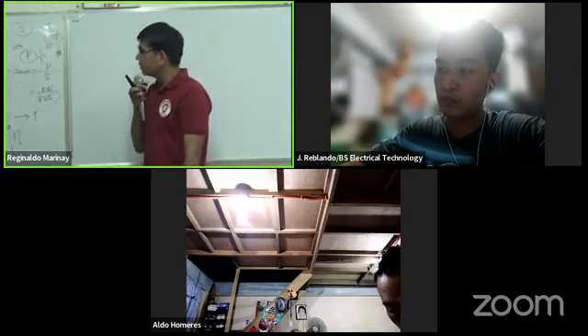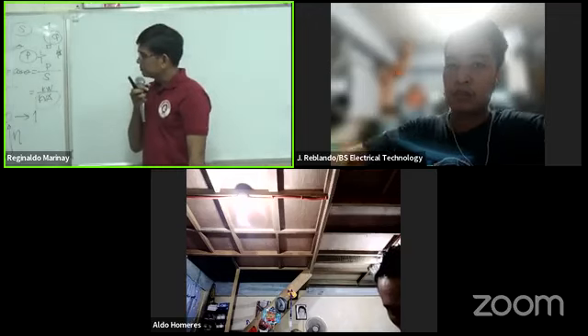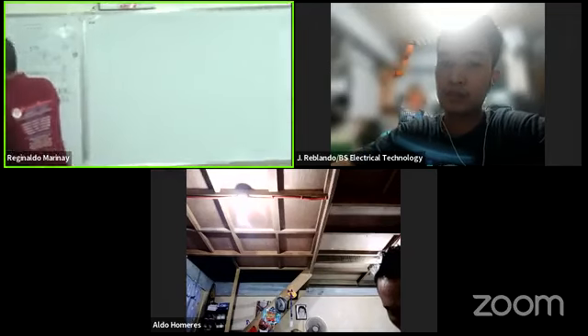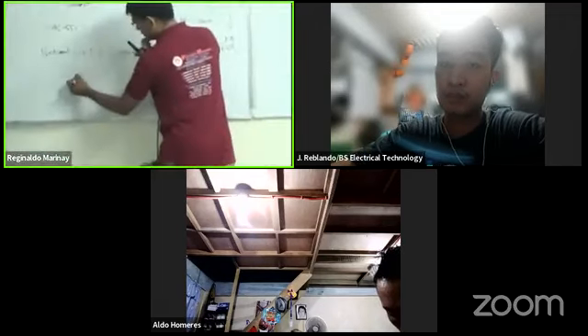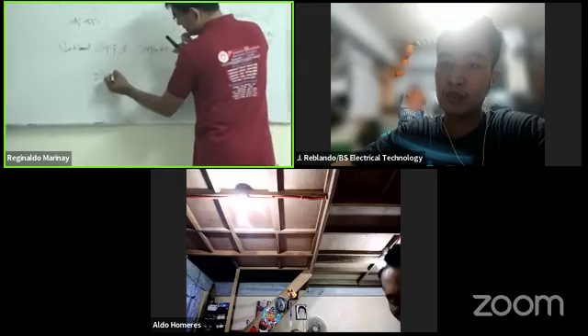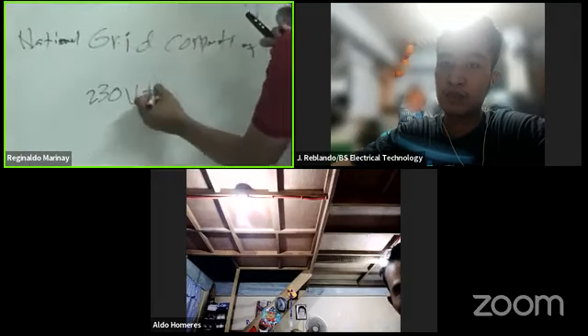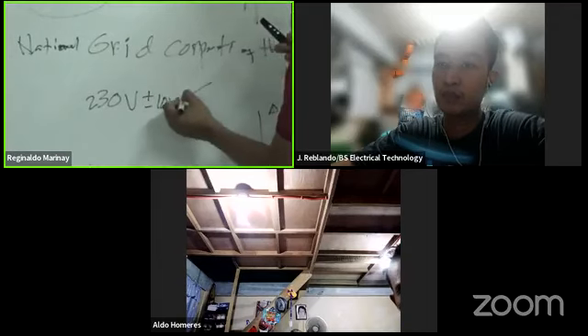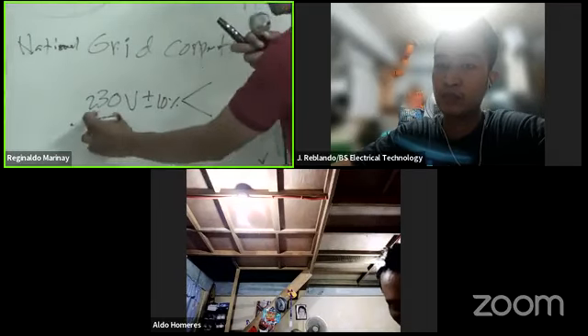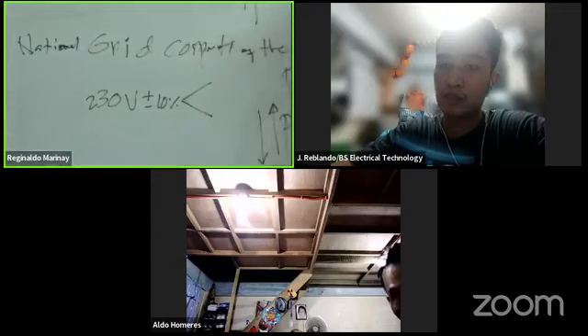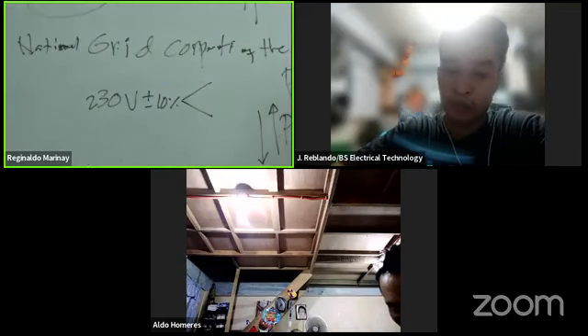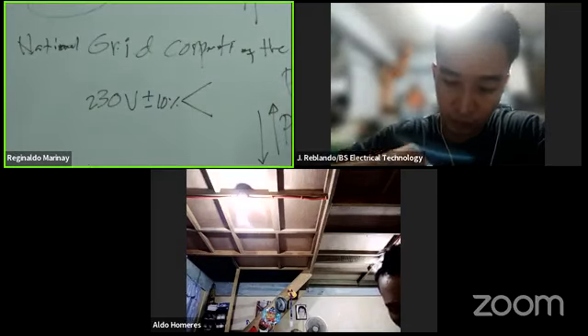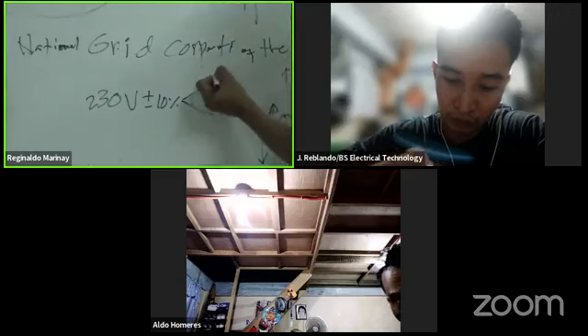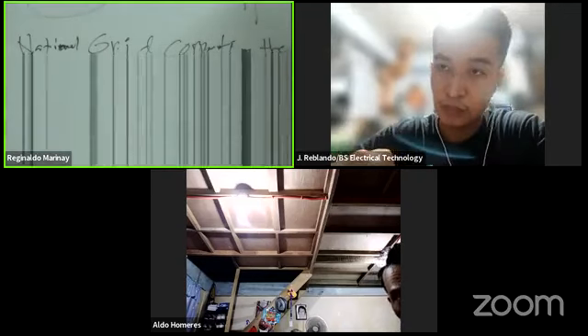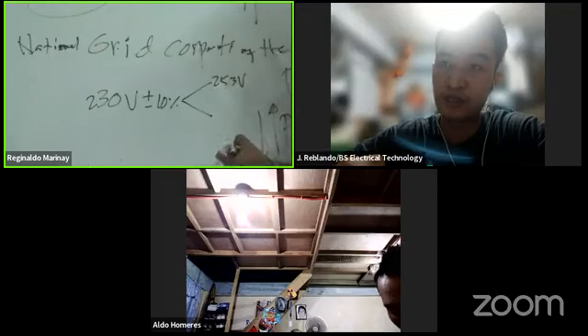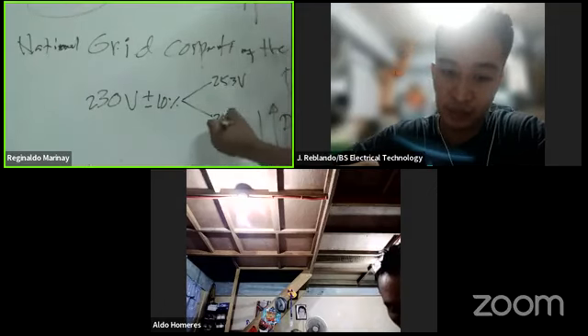If your voltage is 230 volts, the Energy Regulatory Commission says it should not exceed plus or minus 10% of this. So what is the upper limit? That is 1.1 times 230. You can use your calculator—the better. How much is this? 253. Is that correct? 253 volts. And the lower limit is 207.